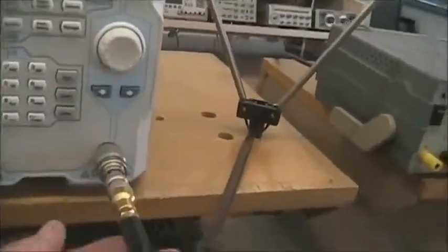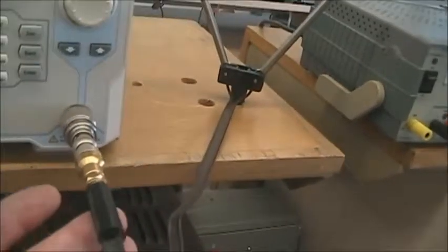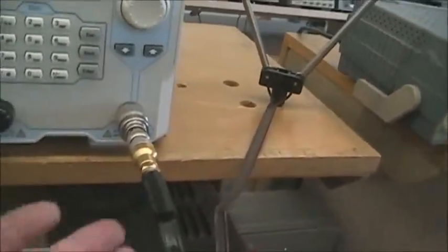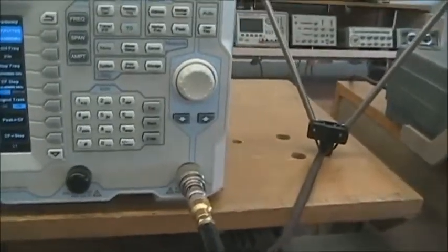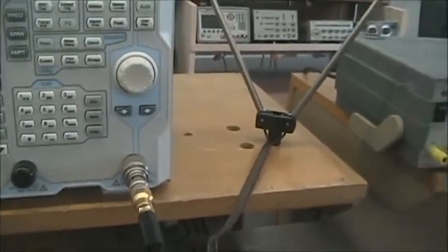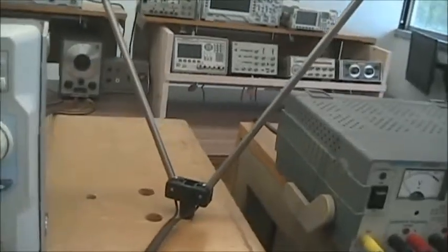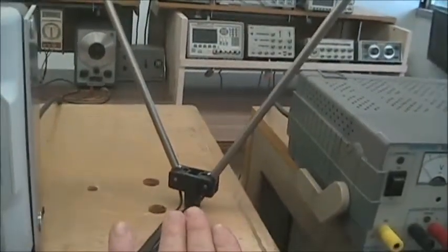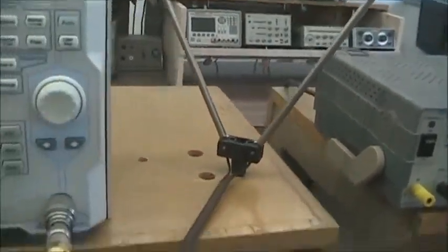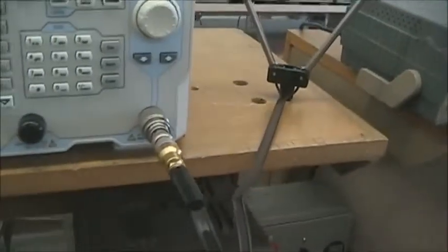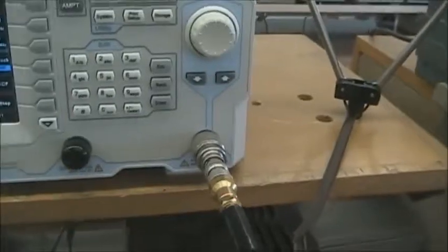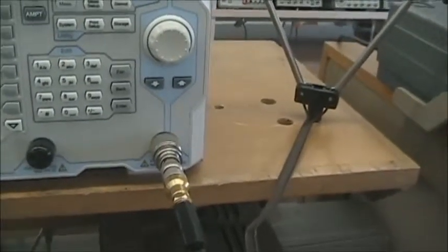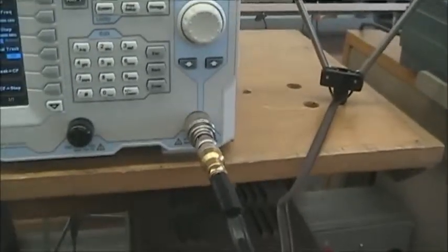I've also got a device between the antenna and the spectrum analyzer called a balun, B-A-L-U-N. That means balanced to unbalanced. So the antenna is a balanced signal, meaning there's no ground associated with that, and this balun is an RF transformer that converts to an unbalanced system, or grounded system. Very important for matching impedances also.